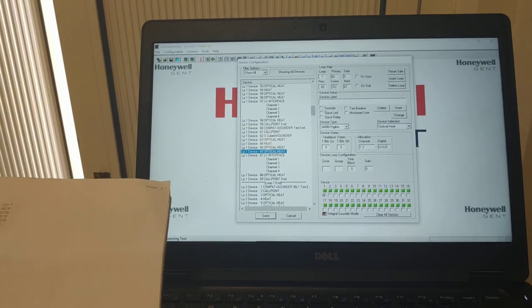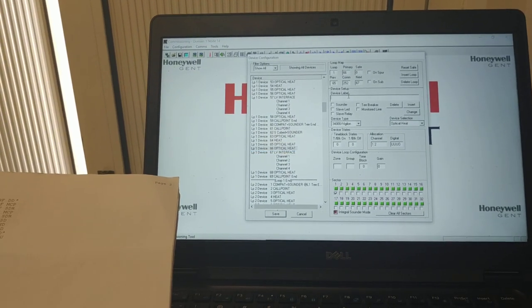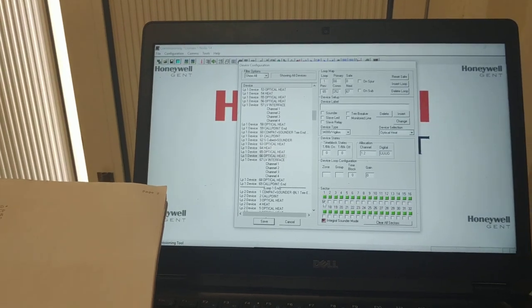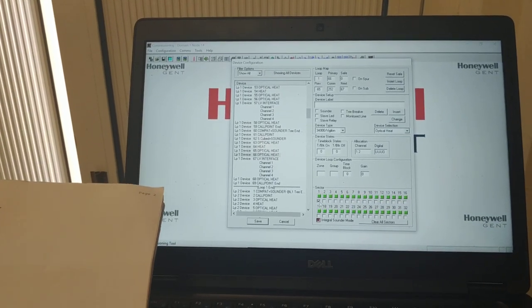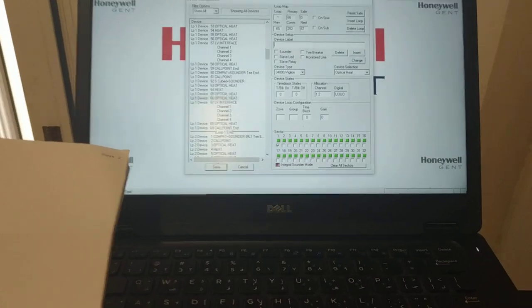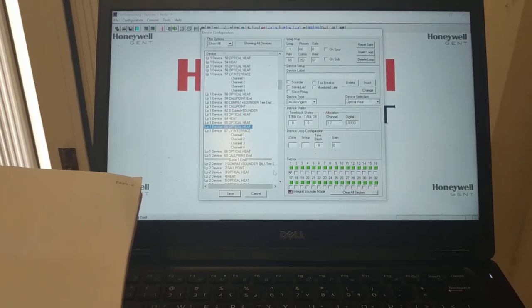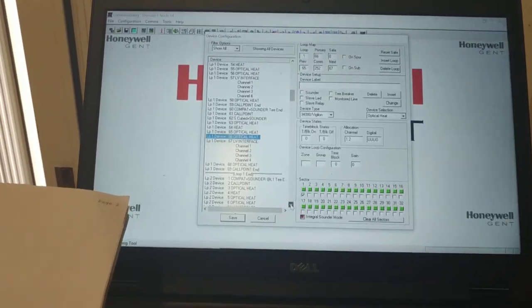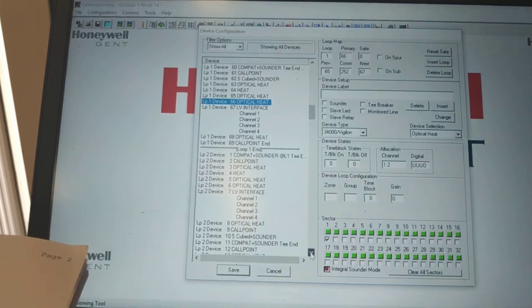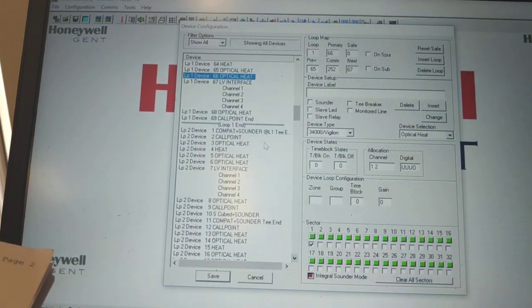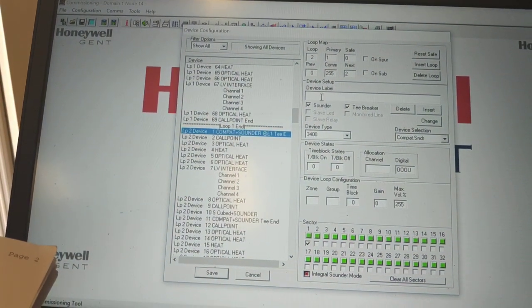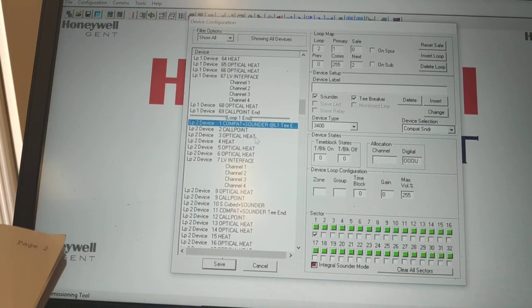There are no labels, and also the sectoring has become Sector 1 for all devices from 1 to 69. There are no labels also. So we need to check Loop 2 — Loop 2 is also Sector 1 with no labels.